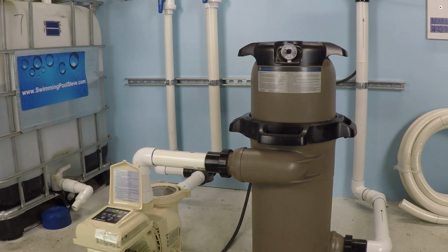If you choose one that's too powerful, you're going to overdrive the filter and potentially damage it. Now, this is especially true if you have a sand filter. Sand filters, typically speaking, have more resistance to flow than either diatomaceous earth filters or cartridge filters. And the reason why is the multi-port valve that's on top or the side of your sand filter. It's a fairly serious flow restriction, and as a result, sand filters by and large have much lower maximum design flow rates that they're able to handle before the filters will potentially sustain damage. And they certainly won't be filtering your water properly.